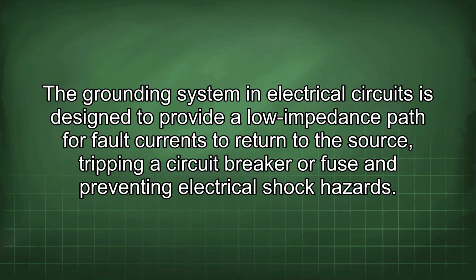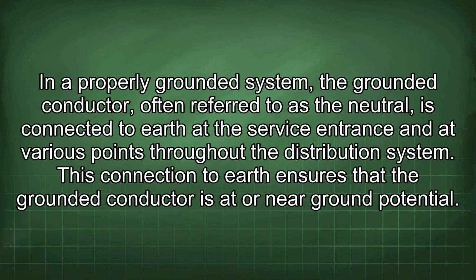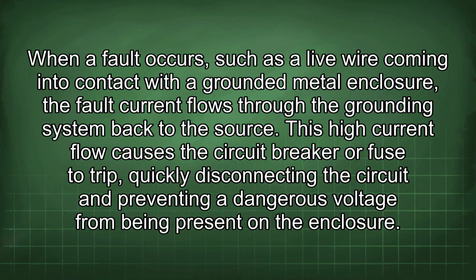The grounding system in electrical circuits is designed to provide a low impedance path for fault currents to return to the source, tripping a circuit breaker or fuse and preventing electrical shock hazards. In a properly grounded system, the grounded conductor, often referred to as the neutral, is connected to earth at the service entrance and at various points throughout the distribution system. This connection to earth ensures that the grounded conductor is at or near ground potential. When a fault occurs, such as a live wire coming into contact with a grounded metal enclosure, the fault current flows through the grounding system back to the source. This high current flow causes the circuit breaker or fuse to trip, quickly disconnecting the circuit and preventing a dangerous voltage from being present in the enclosure.